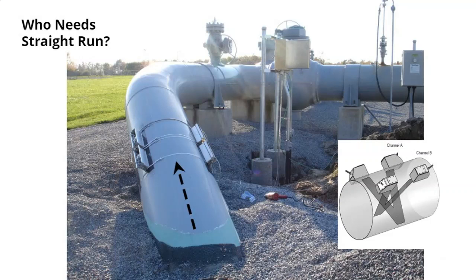And this is what we do. We do something called dual beam. So this is dual beam over here. You can see the 2 sets of transducers here. So what we're doing basically is taking a measurement in 60 to 90 degree opposing planes on the pipe, and we're averaging those to get an average flow through the pipe. This allows us to be used in short straight runs and still be fairly accurate, 1 to 3% accuracy.